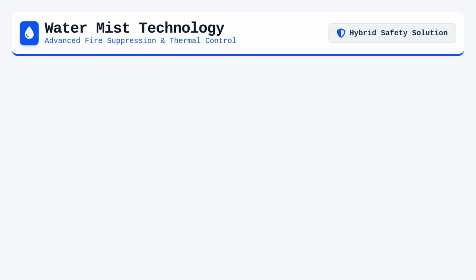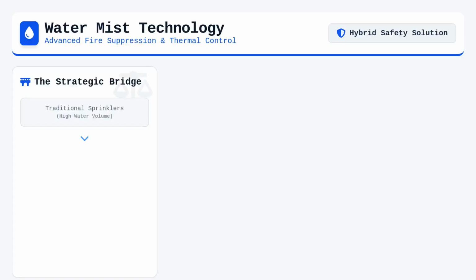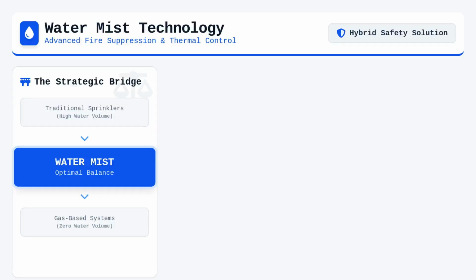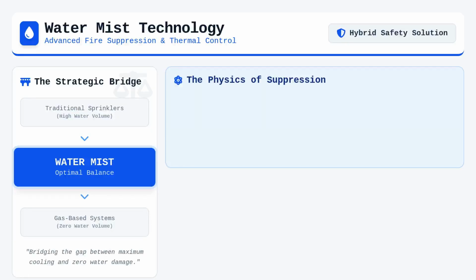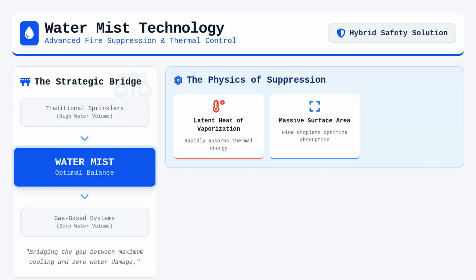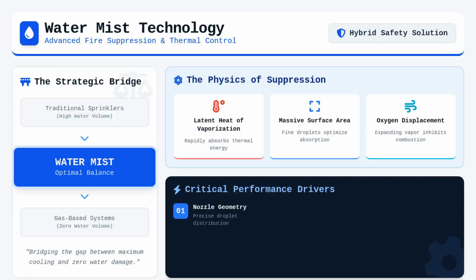Water mist technology serves as an intermediate solution, bridging the gap between traditional sprinklers and gas-based systems by exploiting the latent heat of vaporization. These systems discharge extremely fine water droplets, giving the spray a massive surface area that absorbs thermal energy rapidly while simultaneously displacing oxygen with expanding water vapor. The performance of these systems is tied heavily to the nozzle geometry and the sustained system pressure, which must be high enough to produce the desired drop size distribution.